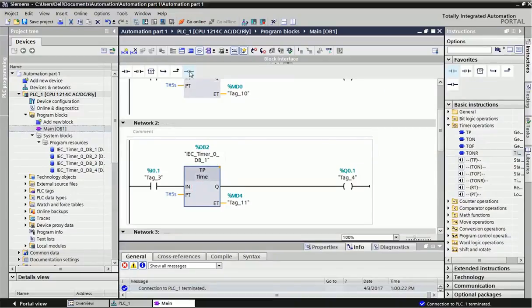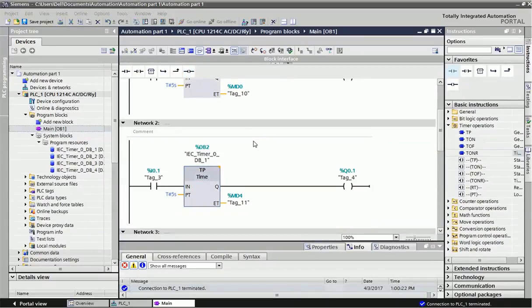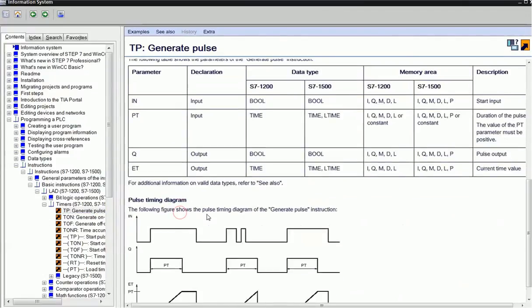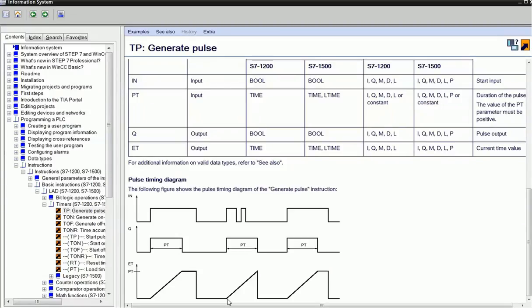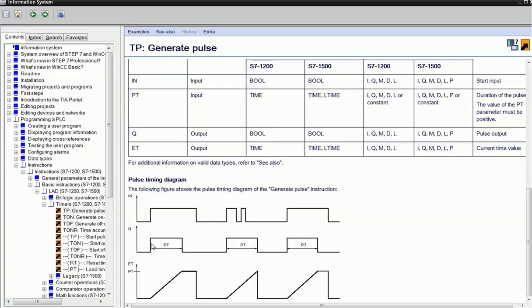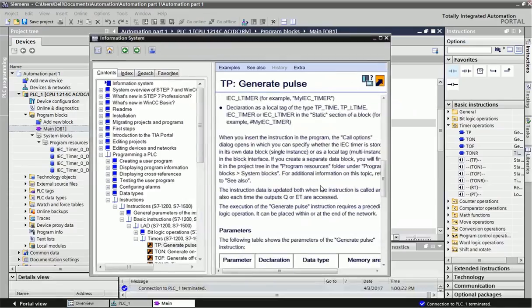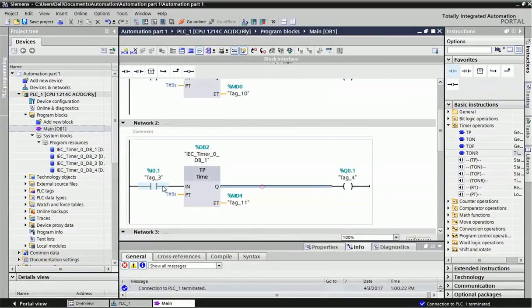The second timer is the Pulse timer (TP). In the TP timing diagram, when I make the input on or give input as a pulse, this timer will start and will remain on for the preset time. After the preset time, the output will be off automatically. In this timer, we just need to give a single pulse - no need to give continuous input.